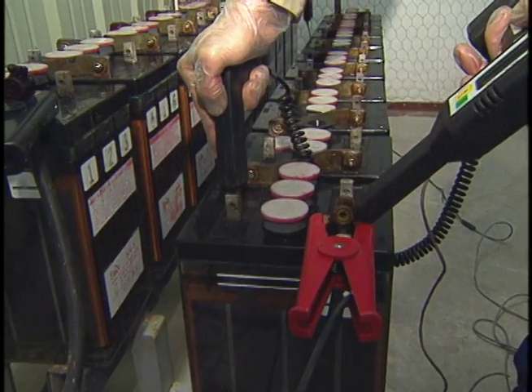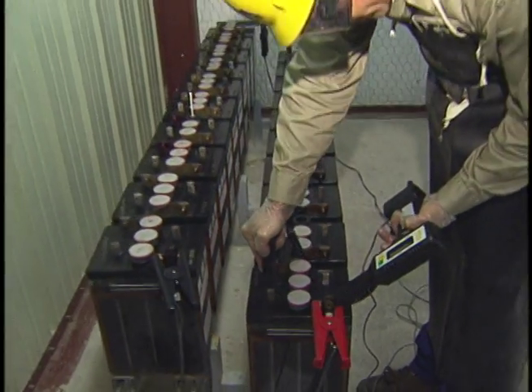Finally, the substation batteries are carefully tested. The batteries are the heart of the substation. Without them, nothing would operate in the instance of a power outage, because we would not have station service. So we have to be sure that the batteries are in tip-top condition.